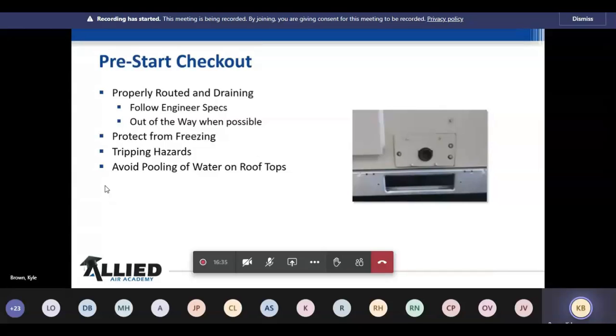And if you're using single or dual enthalpy controllers and the enthalpy is too high and it's not going to allow for free cooling to happen, then your mechanical cooling is going to come on and you're going to have water. You need a way to get rid of that water and protect it from freezing, or you're going to drop water in on that. So that's why it's important to really think about. In residential applications, we don't really care. I mean, we care, but it's not as prevalent.